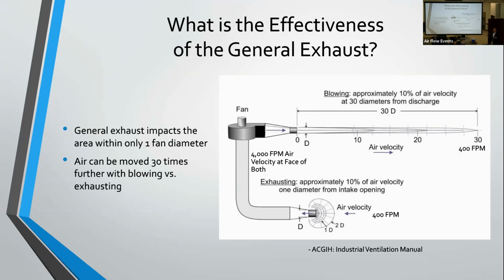Basically, if you're looking at the inlet of a wall fan, an exhaust fan on the wall, where you're pulling the air, you're really only impacting the area of that fan by about 1 fan diameter or so, based on the inlet velocity versus where it's at. So say it's 4,000 feet per minute at this inlet here, 10% of that velocity, which would be 400, would be about 1 fan diameter away when you're trying to pull that air. So not very effective, 1 fan diameter in distance when you compare that to the size of the buildings that we're talking about here.